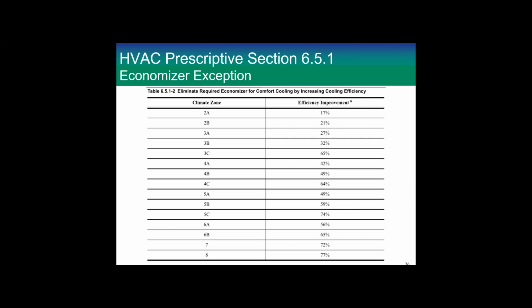All right, if you want to not put an economizer in, these are the numbers we think you're saving by using an economizer. So based on your climate zone, like for 4A, you would have to find a piece of equipment that was 42% more efficient than the piece of equipment we're showing in our tables to be able to eliminate the economizer, or 17% in a warm climate zone like 2A. So the colder the climate zone, the more often you can use economizers, and the harder it is to eliminate them by equipment efficiency improvement.